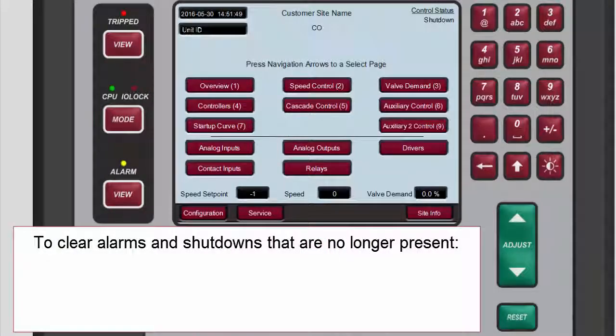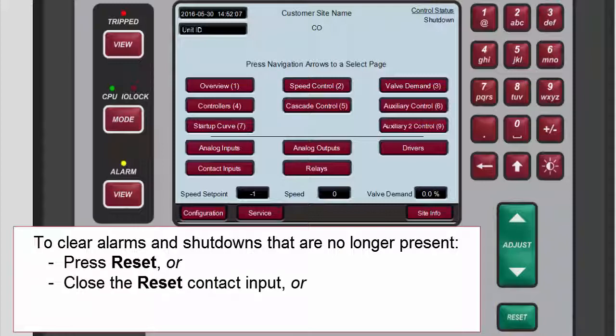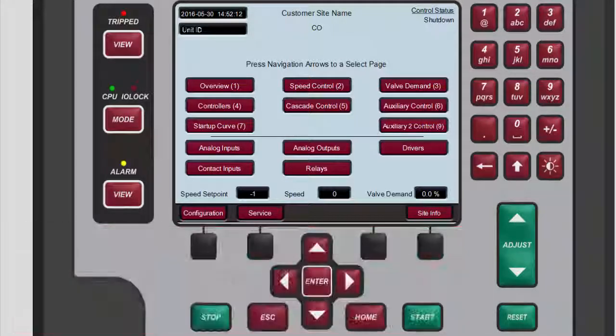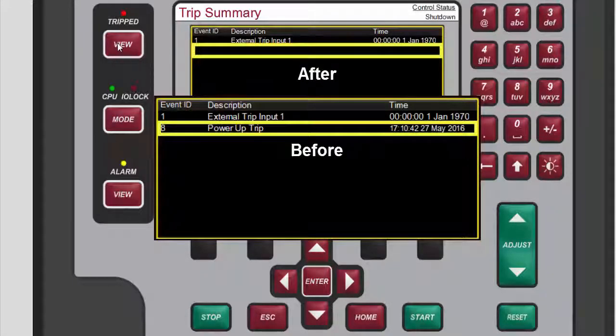To clear any alarms or shutdowns that are no longer present, at any time and from any screen, press Reset on the 505 front panel, or close the reset contact input, or select Reset from either Modbus communications link. If the cause of the event has been corrected, the alarm or shutdown will clear. If not, it will remain and the timestamp will remain unchanged.